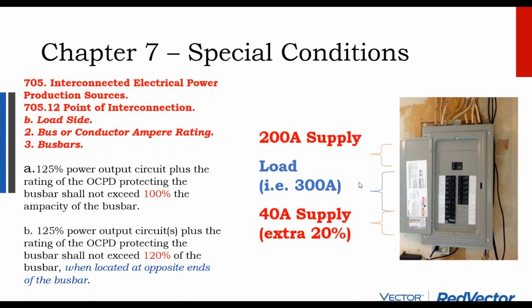Well, if all of these breakers were functioning at full load at the same time, it would, except your main breaker would trip. And if your main breaker trips, you lose power, and the reason this all works is not all the loads on a service panel function at the same time. But if all those loads indeed were functioning at the same time, then you shouldn't exceed the rating of the main breaker.